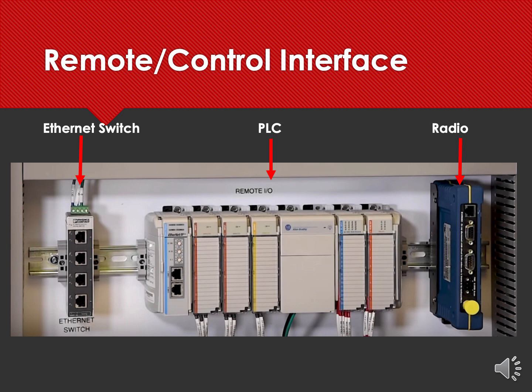On the middle tier of the cabinet, we have the brains of the outfit, if you will. The first thing you see in the middle of the panel is the programmable logic controller in this particular unit. And again, there can be many different kinds of devices, variable speed drives or whatever, all included in this panel. This just happens to be the PLC part of the panel. To the left of the PLC, you'll see the Ethernet switch. This is used where we're connecting, say, Cat5 cable to it to actually allow this system to talk to a different system. And then in the far right side is, in this case, a radio connection, which allows for wireless communication between this part of the panel and other types of equipment as well. And you'll see there's some various Ethernet ports and so on in the radio equipment in the panel as well. So let's go to the next slide.